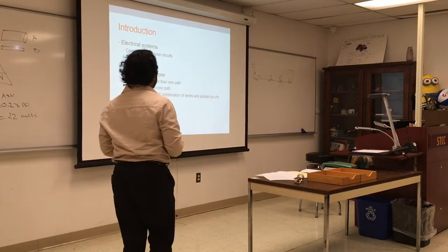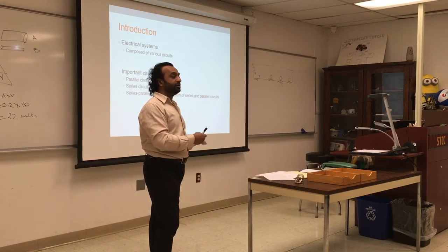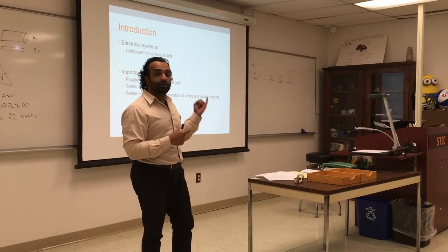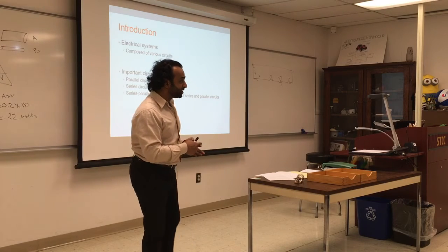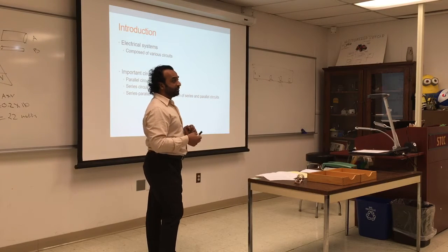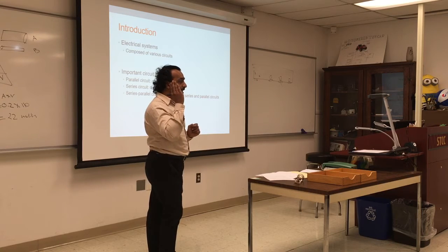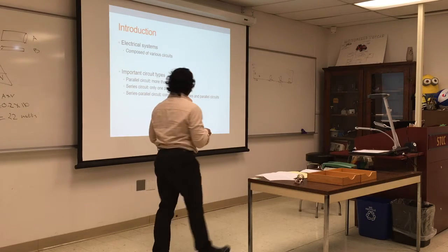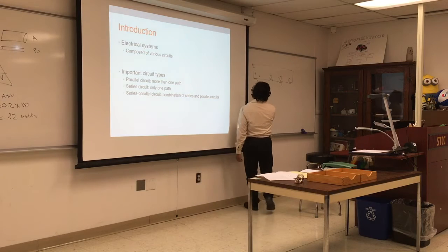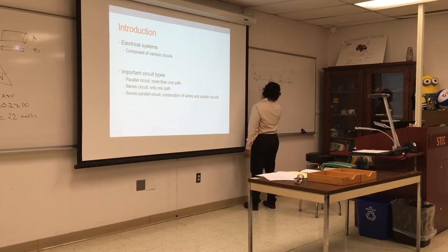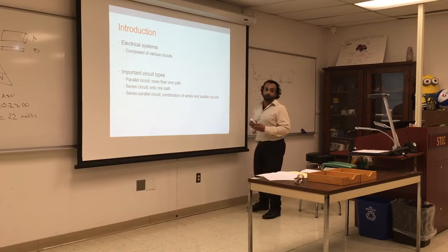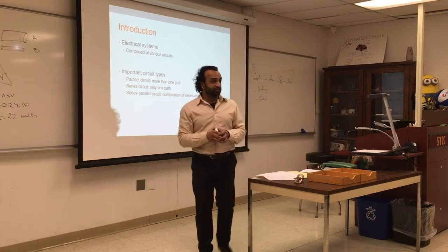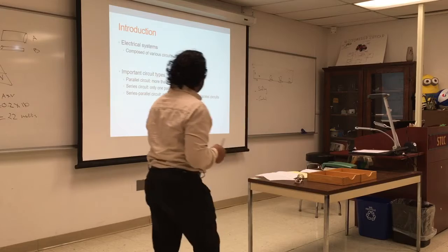So that's a series circuit. We need it. It's not a bad thing. It's a good thing. We need it for safety. If you want to put a fuse, thermal switch, high pressure switch, or low pressure switch, they are going to be in series. Because if any of those pops up, the whole circuit goes down. So series circuit is used for safety and control. The fuse is going to be in series, otherwise there's no need for a fuse. So that's a series circuit.